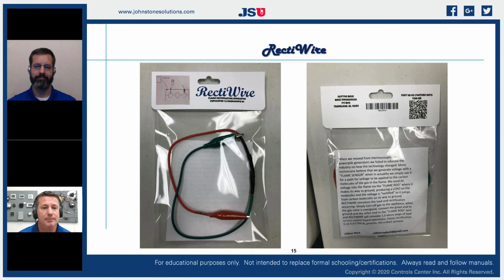So it's very easy to understand flame rectification when we know what's going on. We're not generating voltage like we used to with a thermocouple or power pile. We are simply applying voltage. We are rectifying it as we pass across the flame on our way back to ground. And that is modern flame rectification.